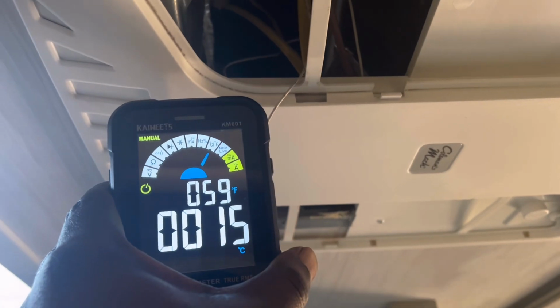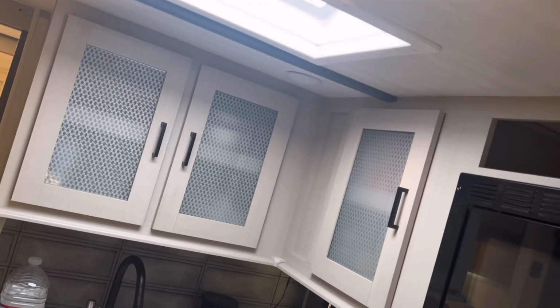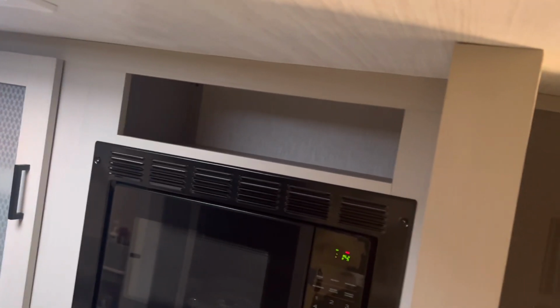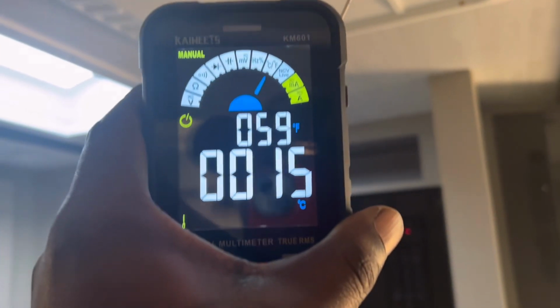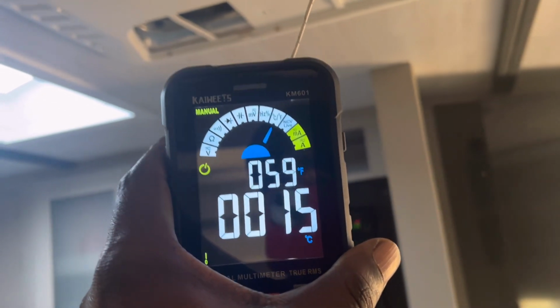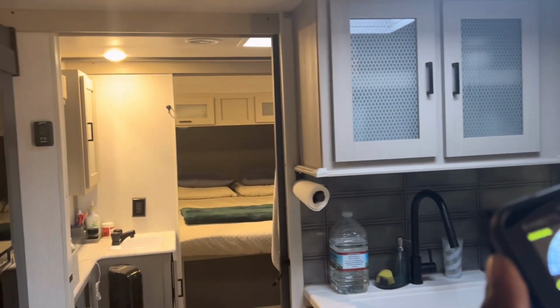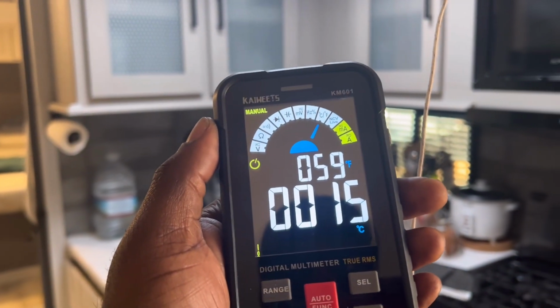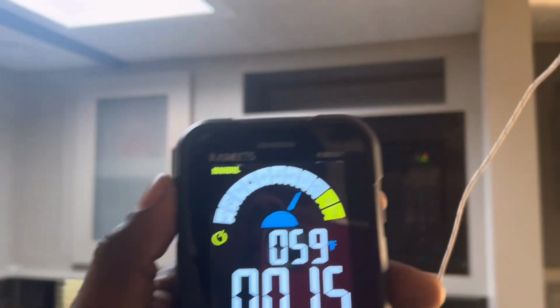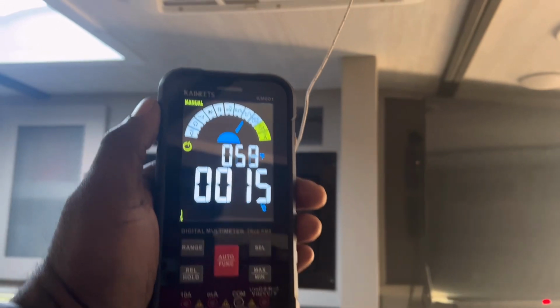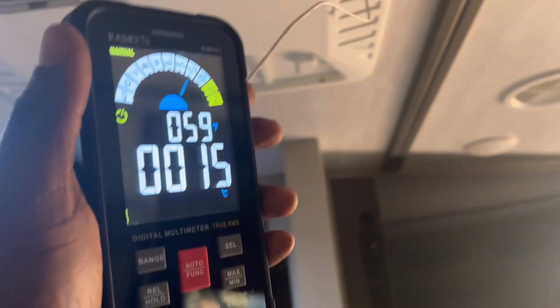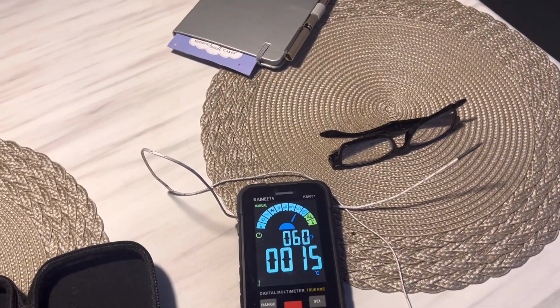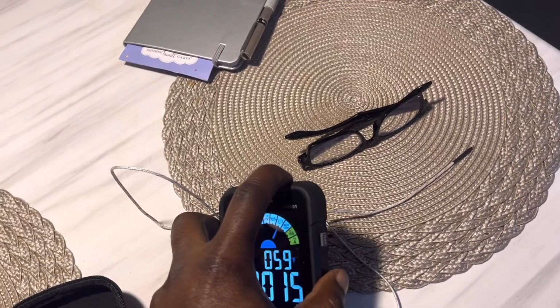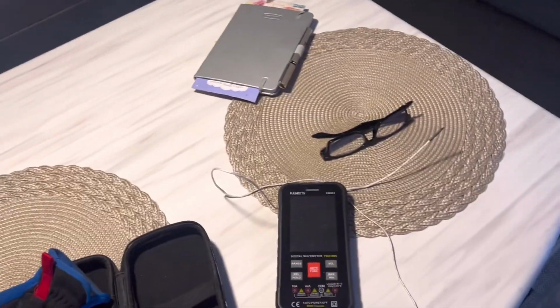So my intake temperature is 60 degrees. Now I need to test my discharge or my supply, and my supply temperature is also 59 degrees, so there is no change. Even though I have the AC set to 33 degrees, which is the lowest setting. So the compressor is not engaging, but at this point, I'm just taking my measurements, and you can see that it fluctuated to 60 degrees. Okay, so the next step is to go on top of the roof and take electrical tests and measurements, starting with voltage. So now I will remove my temperature probe, and we're still at 60 degrees. So the return and the supply are the same temperature, which means that the cooling unit is not cooling. So now we need to go on top and see why.